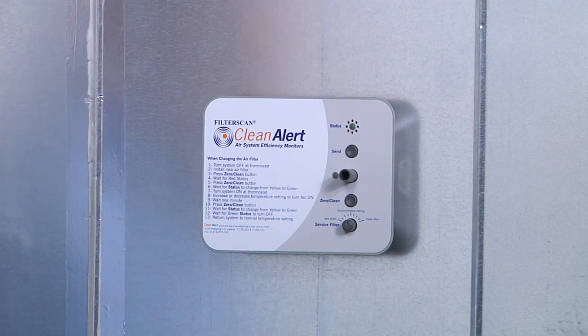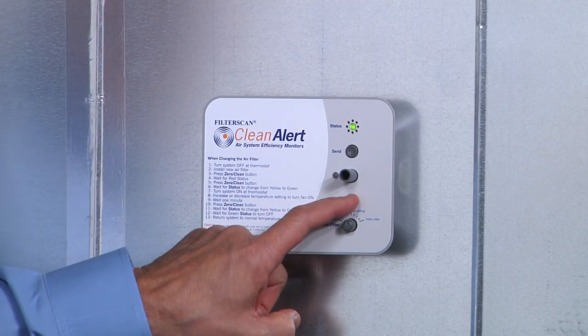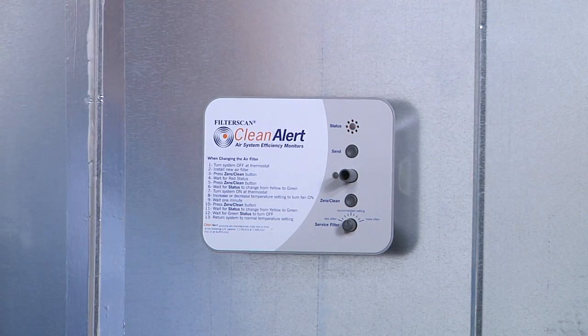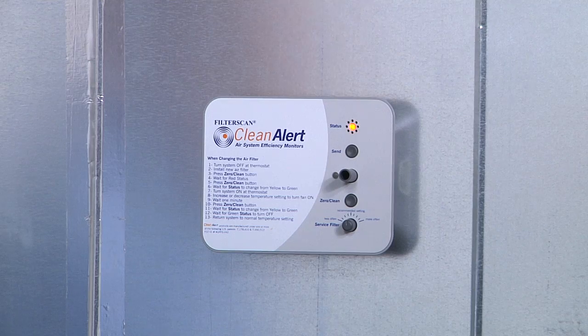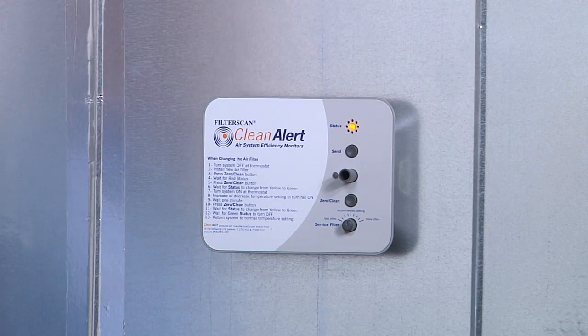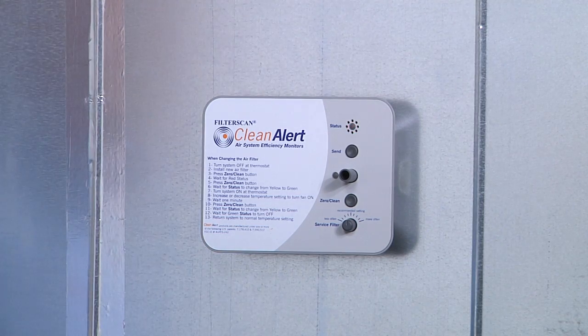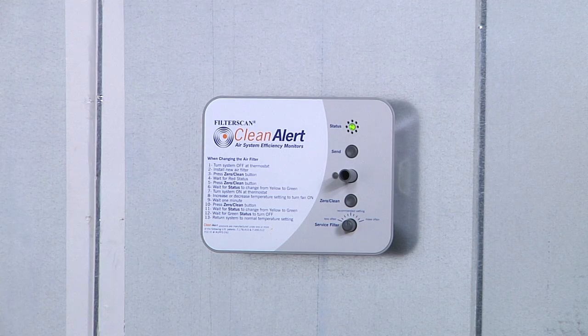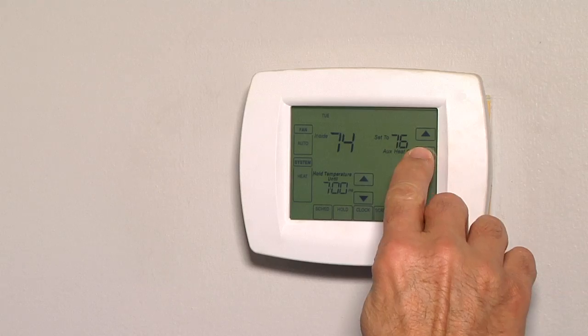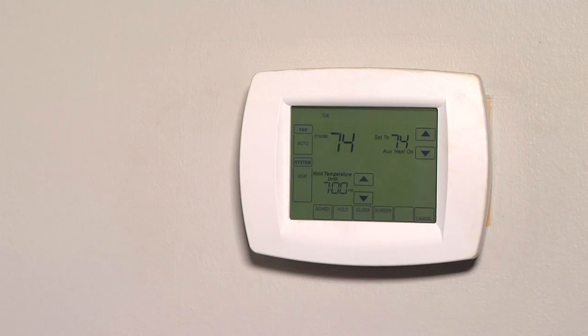Once the HVAC system blower fan turns on, wait 1 minute for the blower fan to stabilize. Depress the Zero Clean button again. The status LED should turn from blinking green to blinking yellow for several minutes. This indicates that the unit is calibrating itself to the air filter and HVAC system into which it is installed. Once calibration is completed, the status LED will blink green a few times, then turn off. Return the thermostat to normal operating temperature. This concludes installation of the Filterscan monitor.